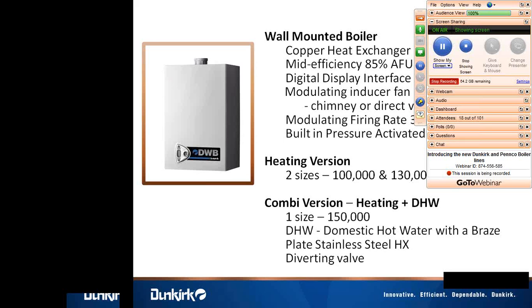Again, it's a coated copper heat exchanger. It's Category 1 or Category 3. It can be sidewall vented using high-temperature stainless, AL294C. The contractor does have an option to bring outside air into the boiler if he wants to make it a sealed combustion system. Or they can vent it into a chimney. Now, the chimney has to be lined with an aluminum liner kit, and the contractor would use B-vent to go from the vent outlet of the boiler to the chimney itself.